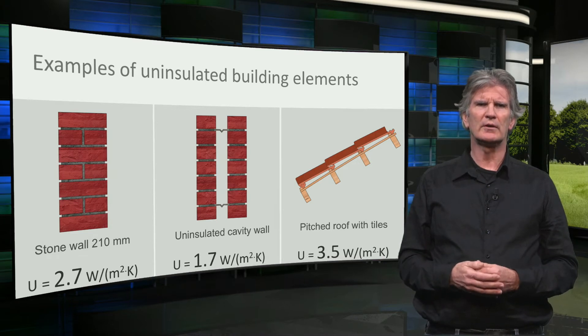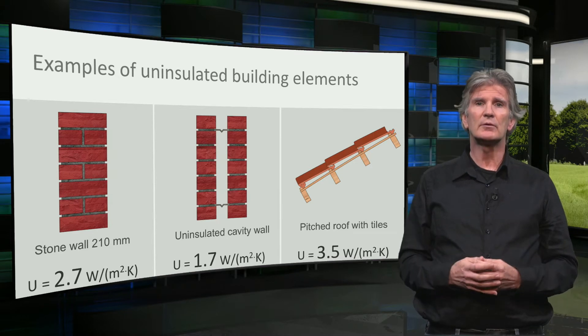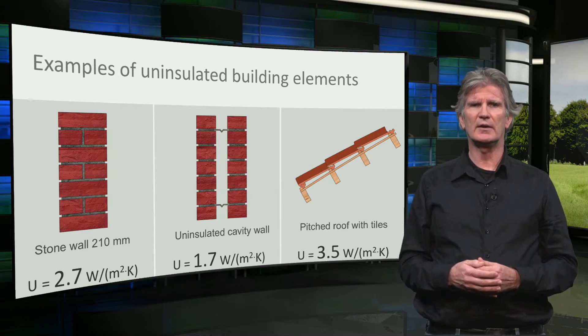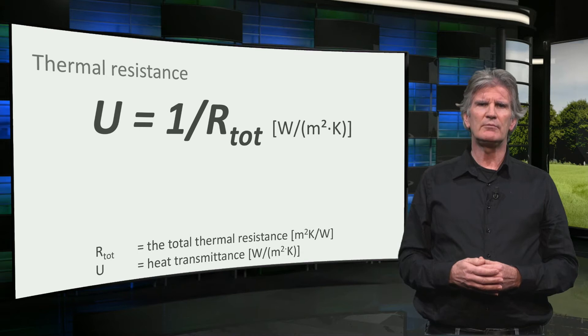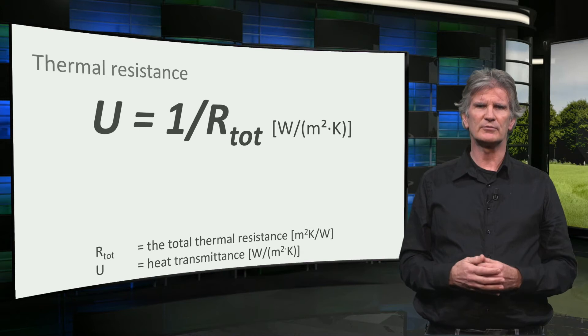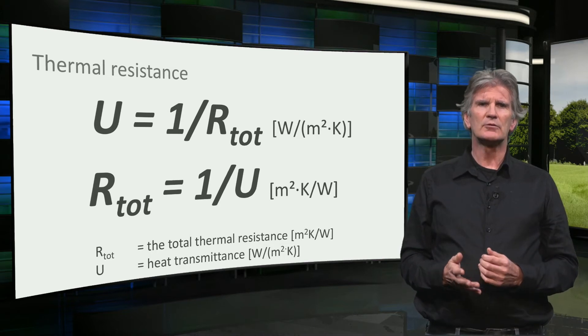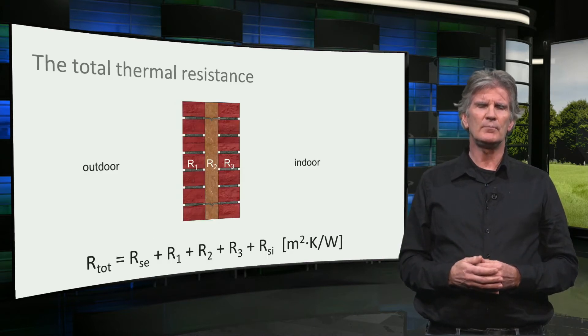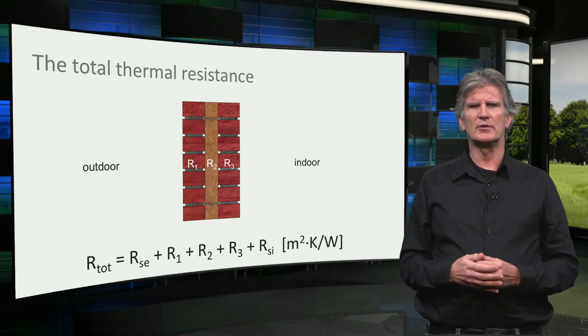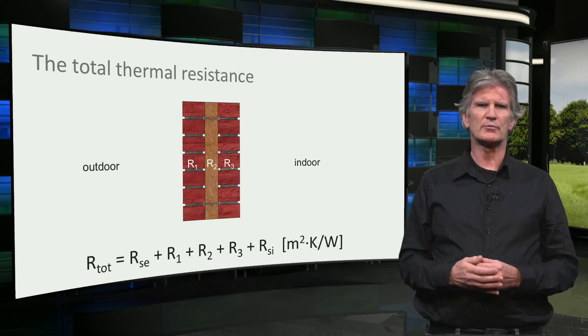How can we reduce the U-value of these uninsulated building elements? For that we have to look somewhat deeper into the U-value of multilayered building elements. The U-value is 1 divided by the total thermal resistance of the construction. The total thermal resistance of a wall is composed of the resistance of the individual layers, with an extra resistance on the inner and outer surface called the surface resistance.